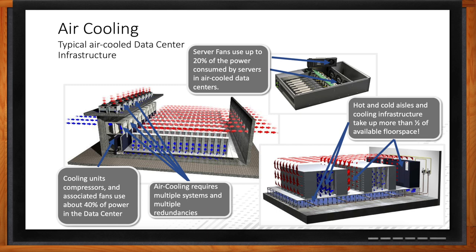On top of that, you've got the additional cost of those HVAC units, and you have to have redundancies — if a cooling unit goes down, you can't have the temperature in your data center go up. Also, on the right-hand side you can see that a typical data center will have a hot aisle and a cold aisle built into it, and that additional space required is actually taking up about half of your available compute space, so your overall density is a lot lower than it really could be.